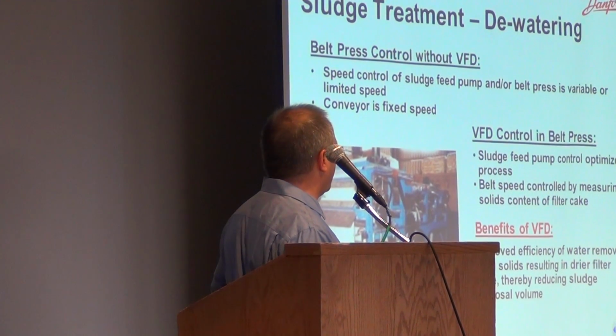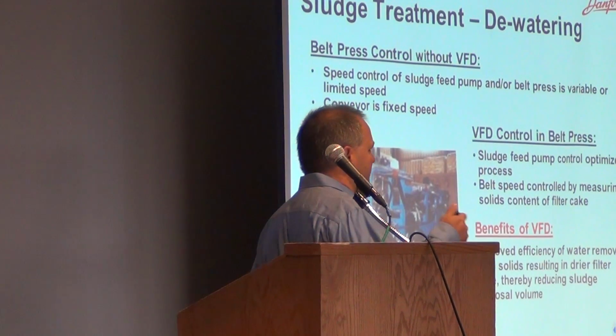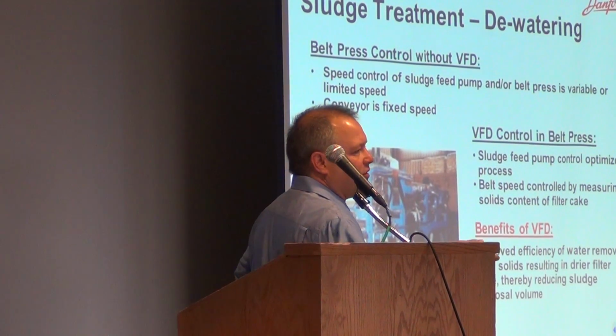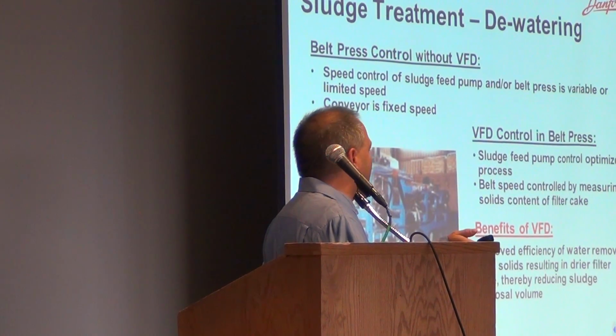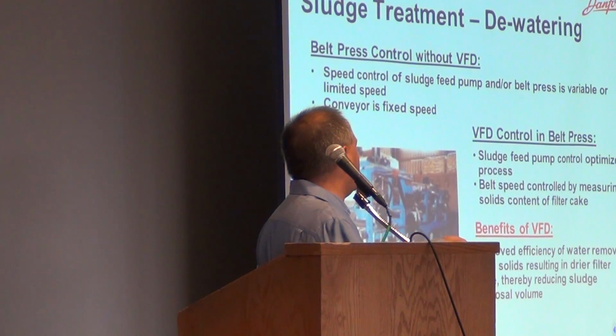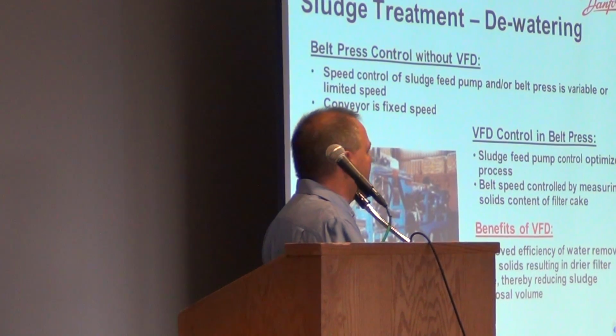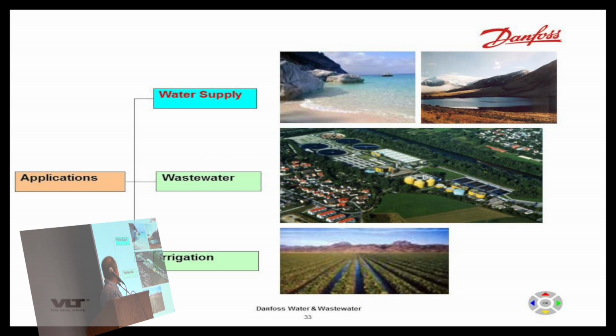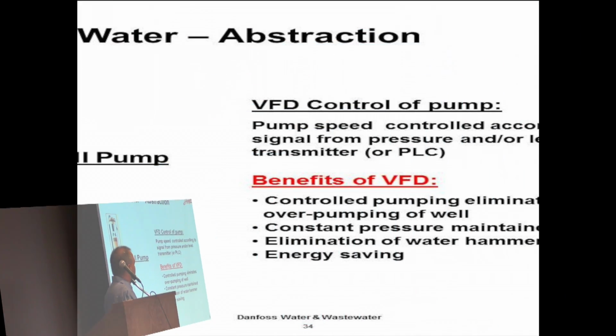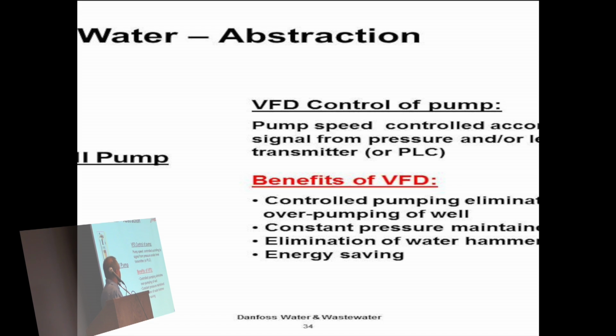Basically, we're just controlling the speed of the unit, so it's like a drier cake. We're looking for less moisture that you're having to send to the landfill. The more water you can get out of the cake, the cheaper it is to use. At the beginning, we talked VFD groundwater, submersible pumps. You can run many cities with drives on their submersible pumps to give you constant pressure. We eliminate the water hammer.